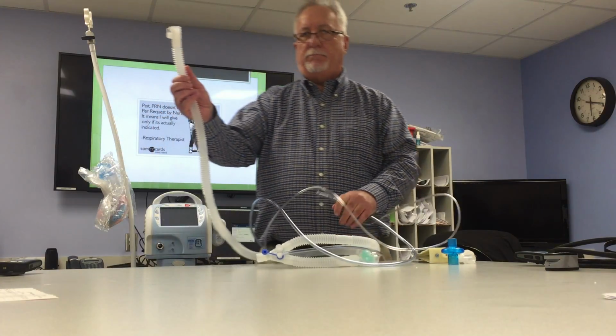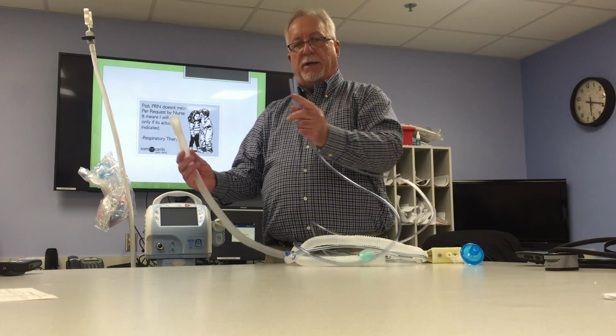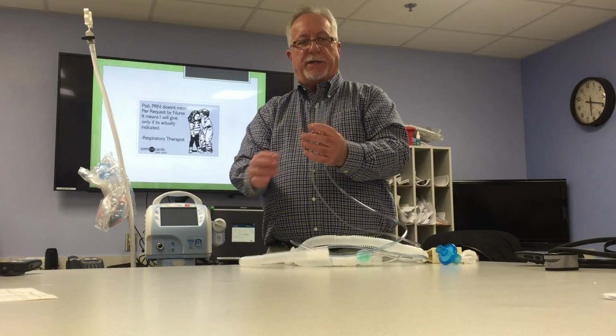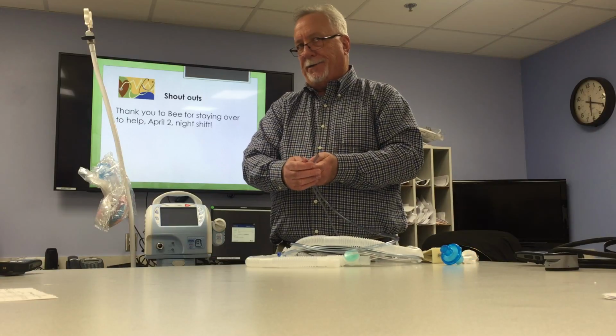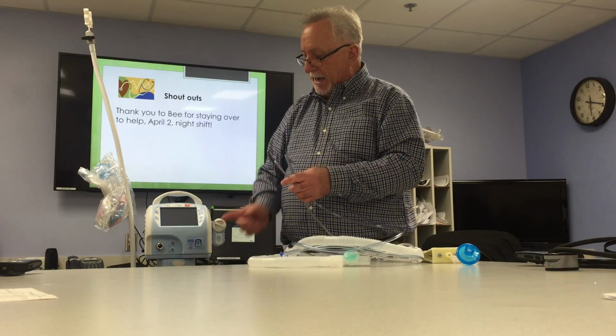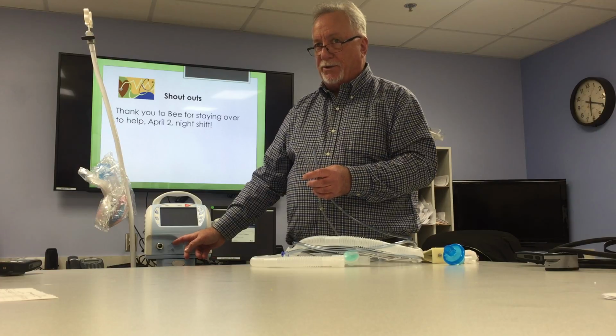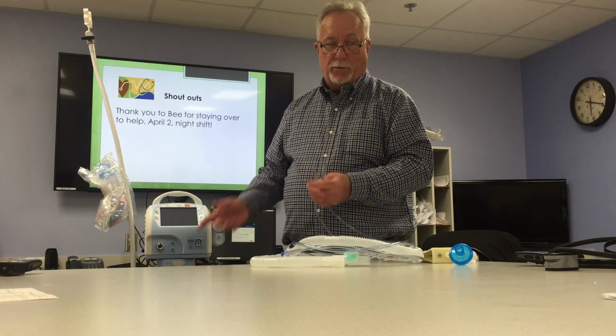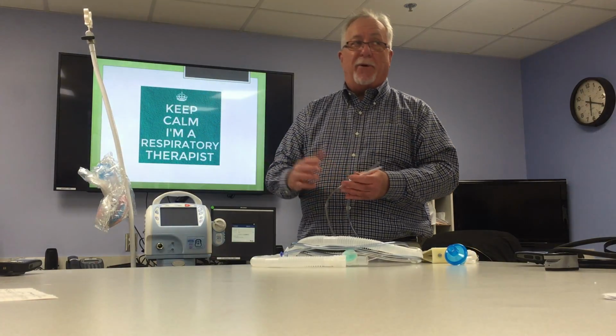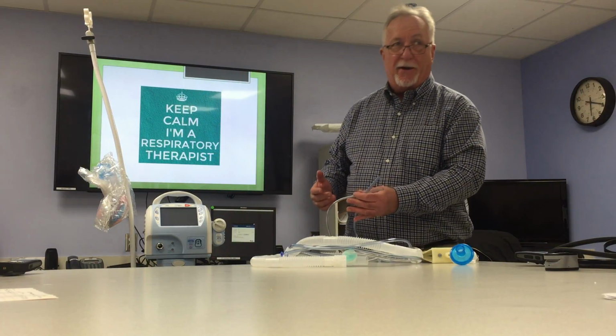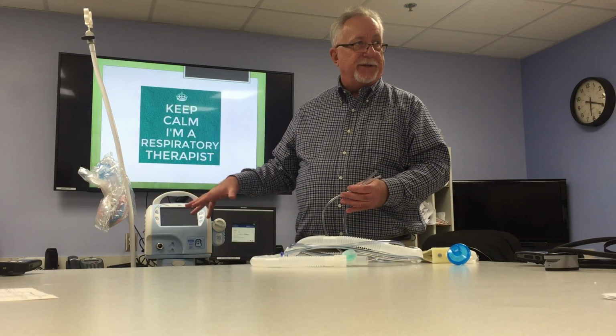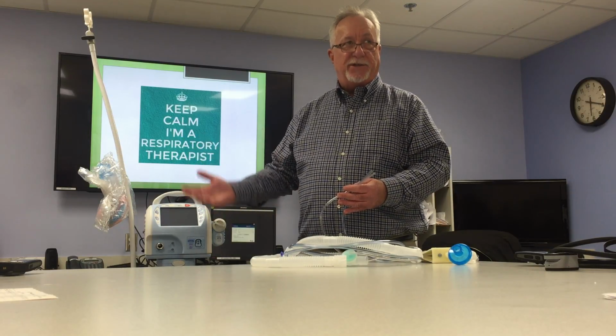Okay. You have 3 connections. So you have your large bore tubing connection, then you have your 2 small tubing connections. Nice thing about this, you can see they're 2 different diameters. So it's kind of, I want to call it dummy proof. You got 2 posts here. One's a larger post, one's a smaller post. So we can figure out pretty quickly what goes where. And remember, going back to the emergency preparedness, you may have non-clinicians setting up ventilators, making changes on the ventilators. So it's designed really for clinicians and non-clinicians alike.